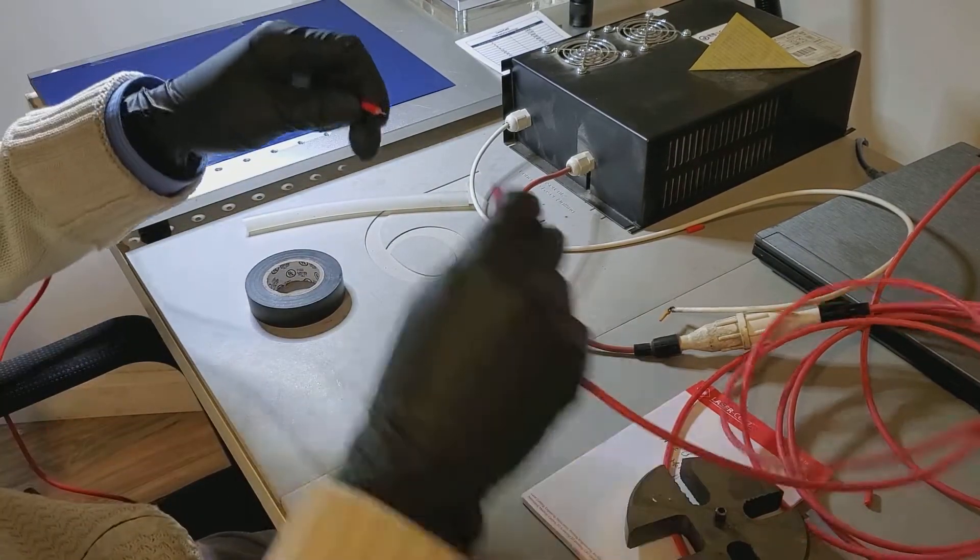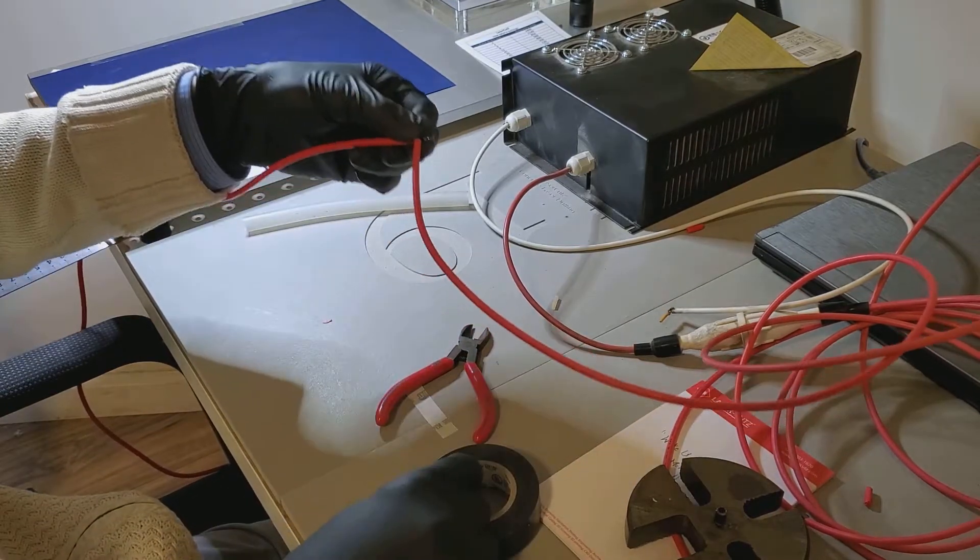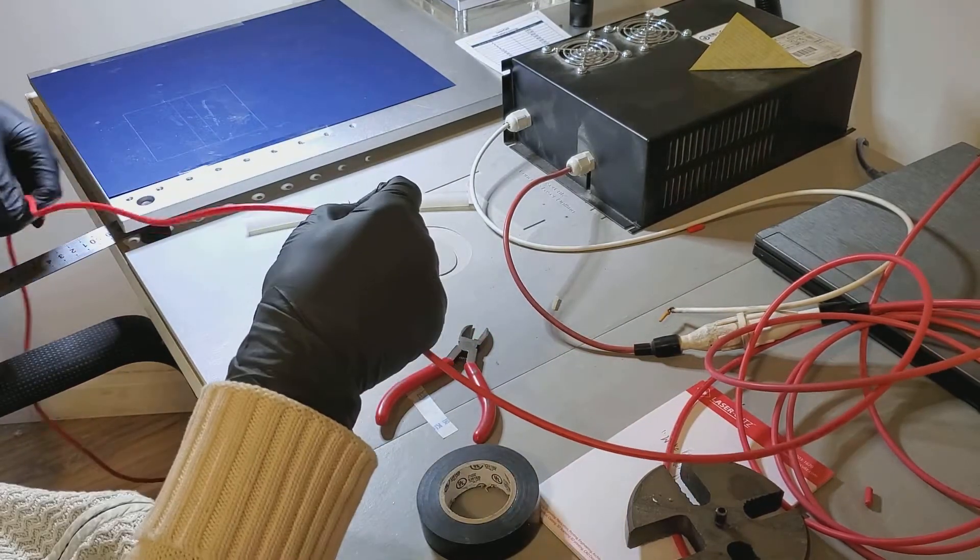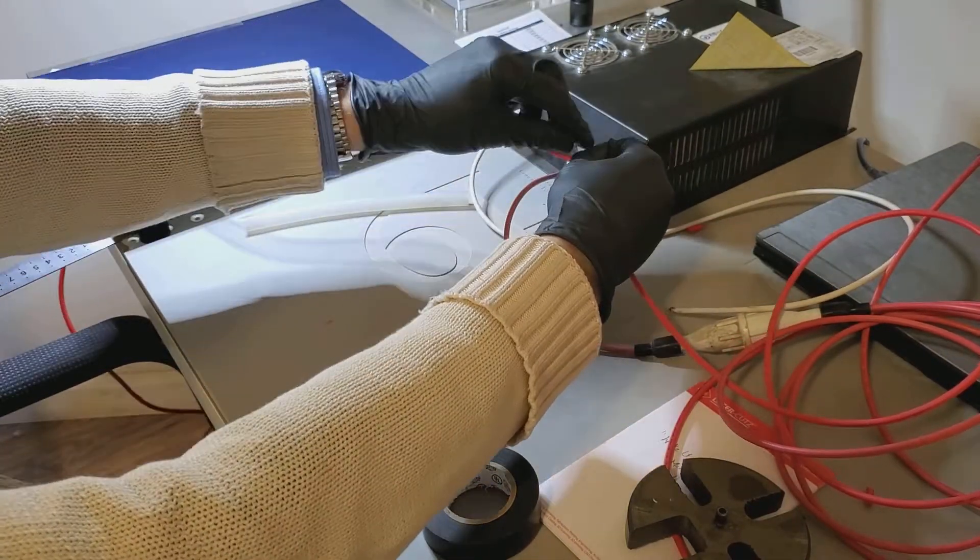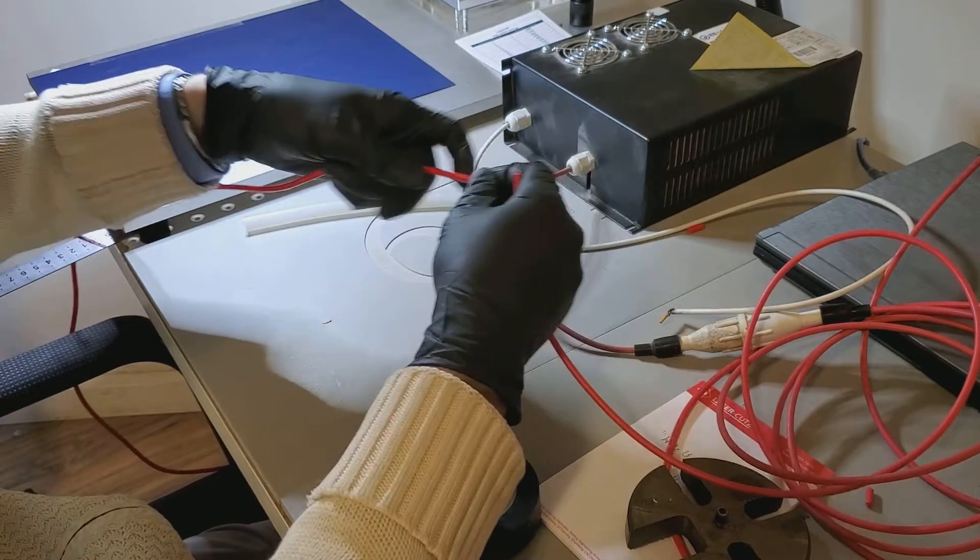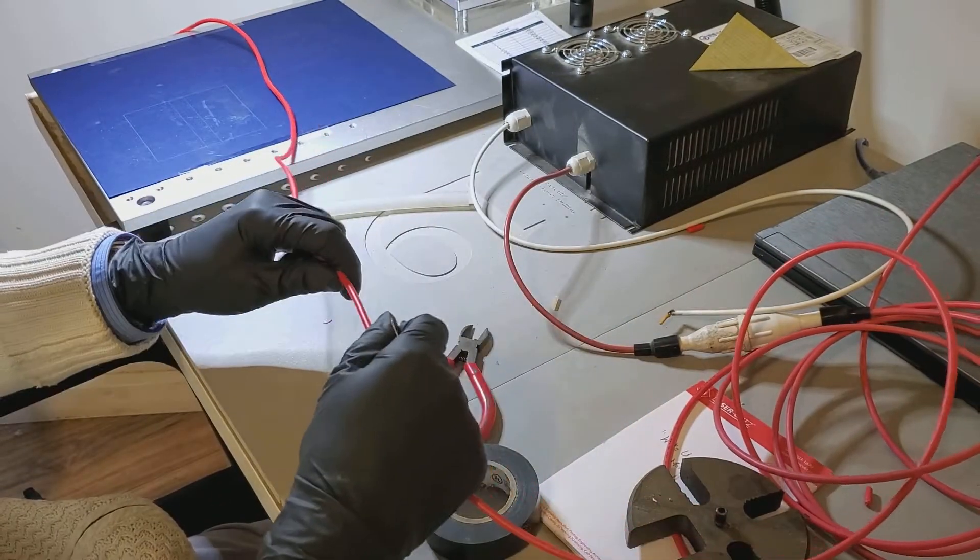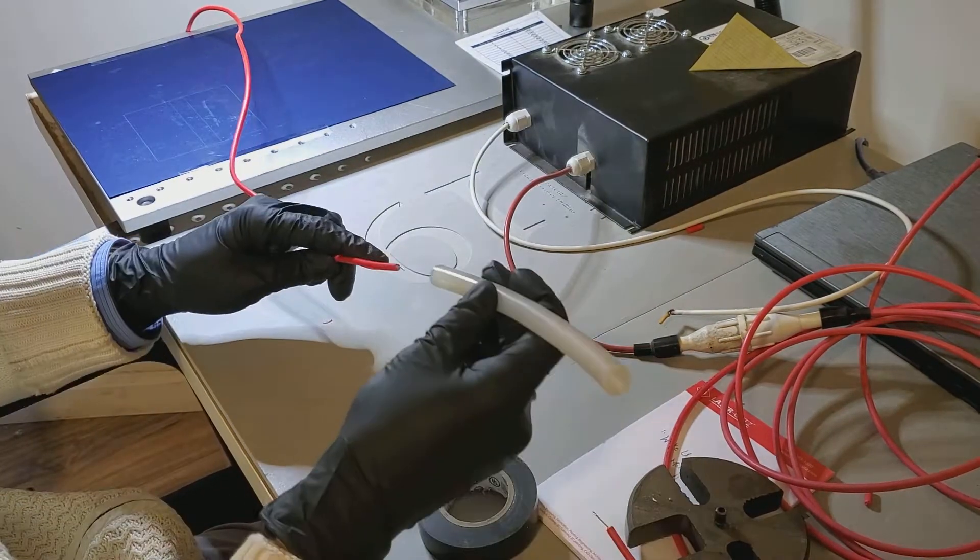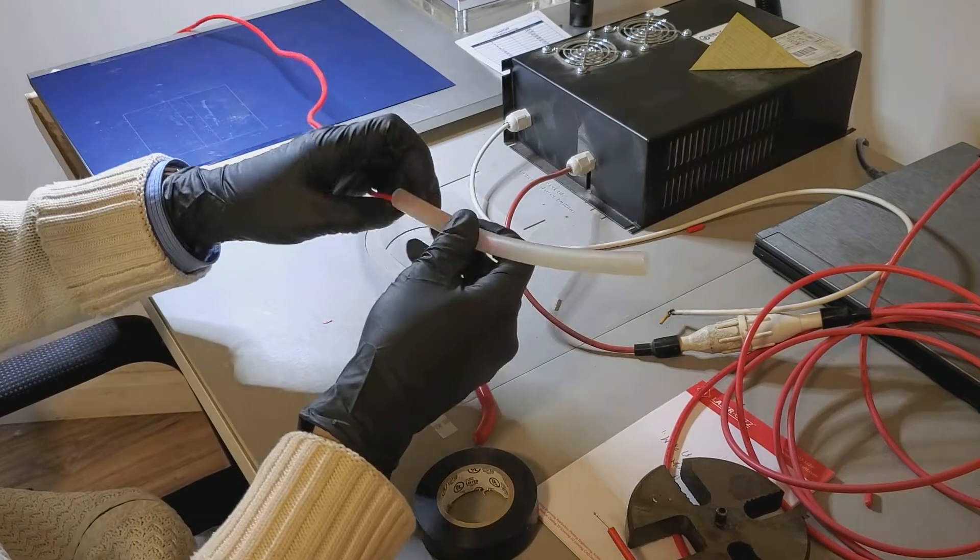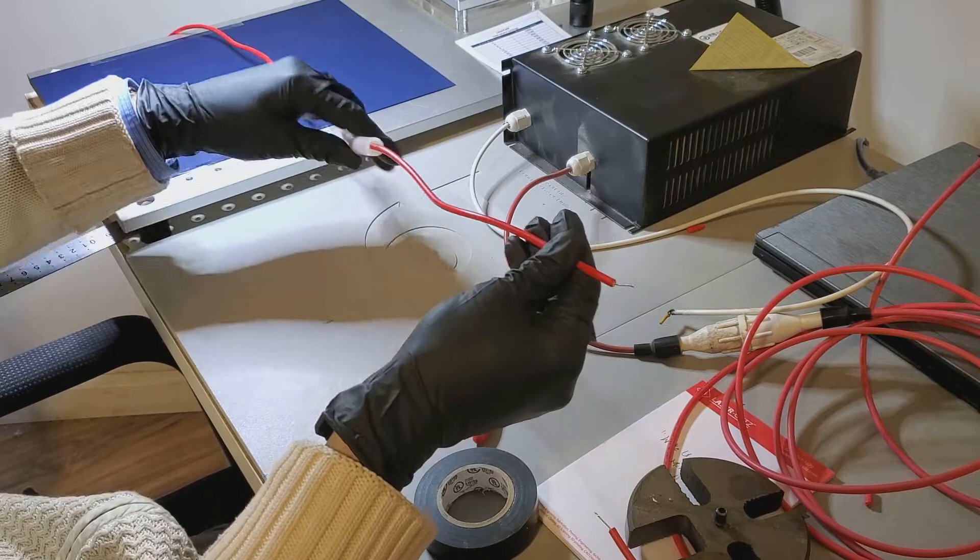If you're going to just do it like this and put electrical tape over it—looks nice, works for your 110 volts—but once you get close to metal, you're just going to arc through the electrical tape. Electrical tape does nothing for that voltage, so you need to do much better insulation. So I cut this one from my tube. Before I do anything, I'm going to put my silicone over the wire, because otherwise I'm going to have to do the job again.